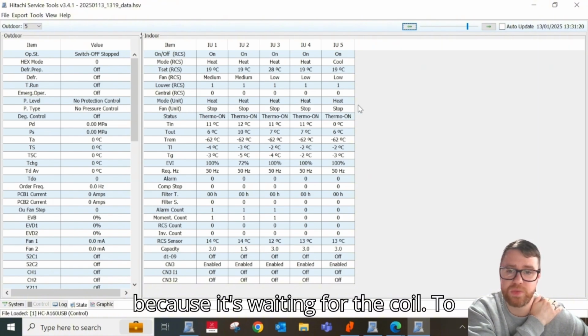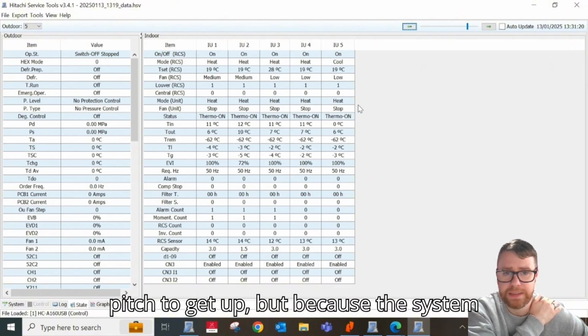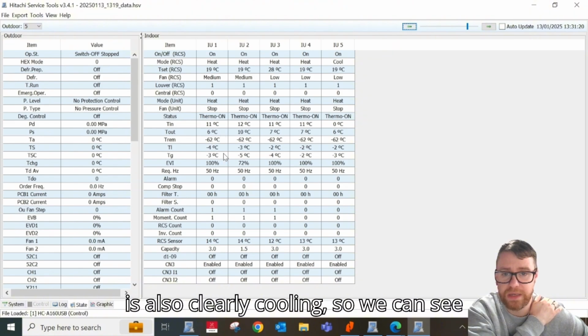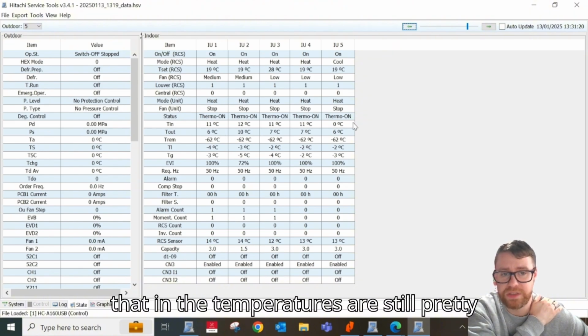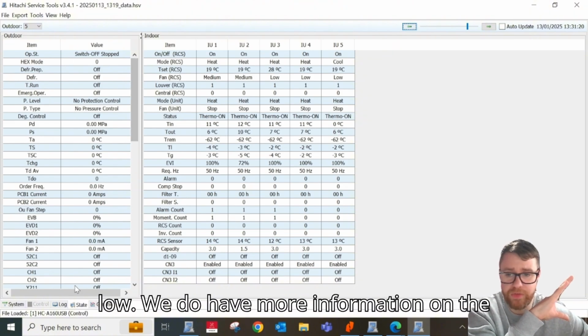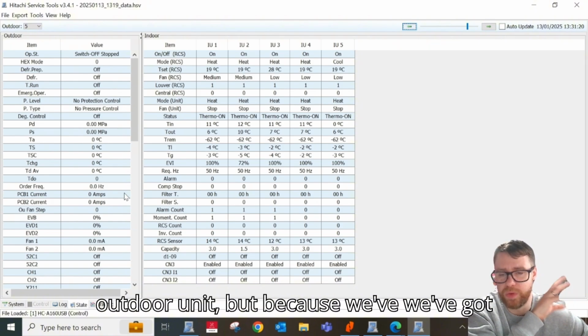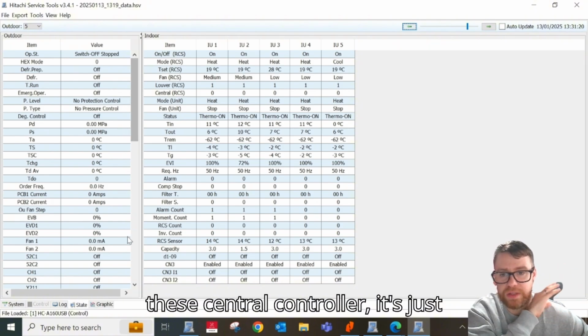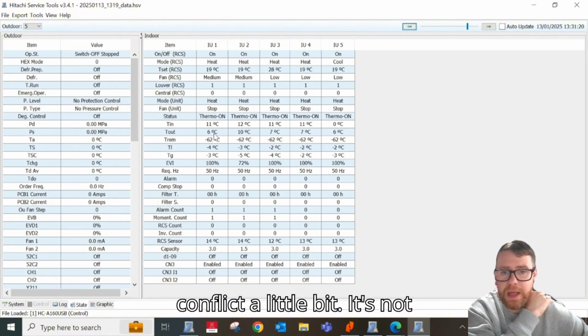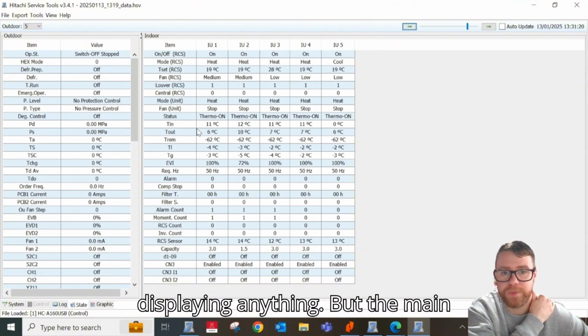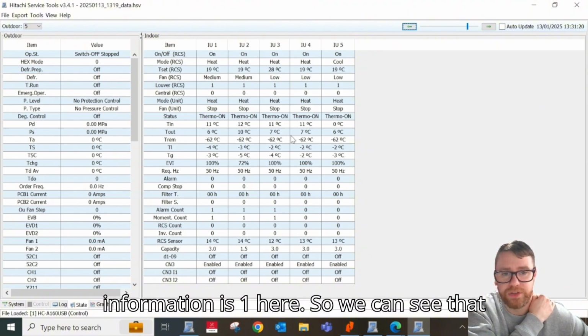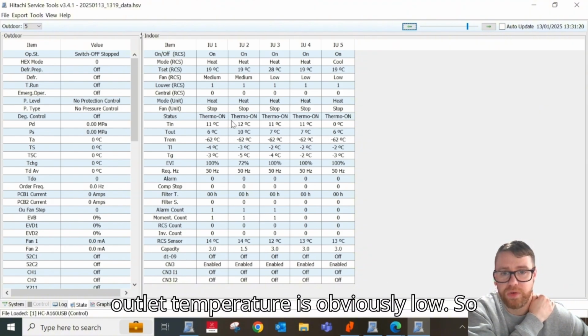The reason is that it's waiting for the coil temperature to get up. But because the system is clearly cooling, we can see that the inlet temperature is still pretty low. We do have more information on the outdoor unit, but because we've got the central controller, it's conflicting a little bit and it's not displaying anything. But the main information is what we want here. We can see the outlet temperature is low, so we're obviously in cooling.